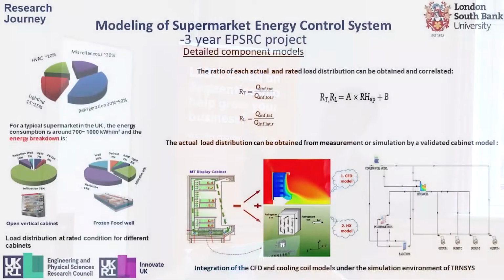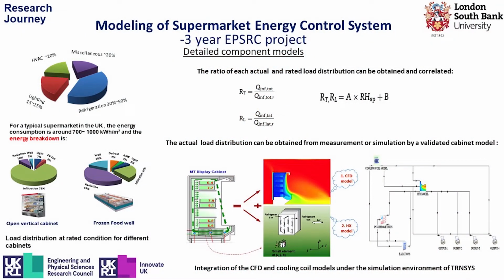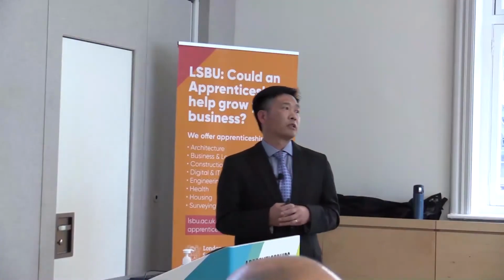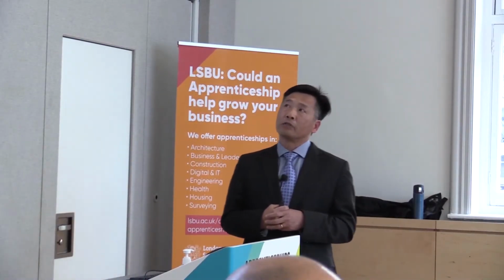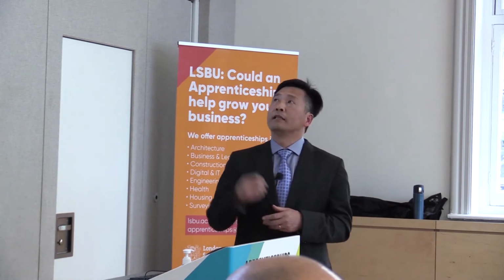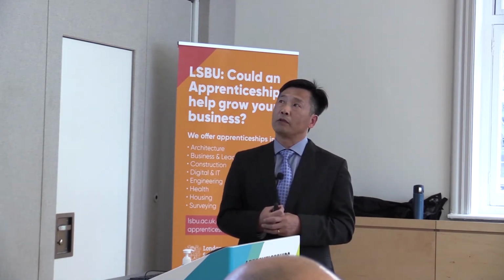So on the top left, you can see the energy breakdown of the supermarket energy control system. Refrigeration will consume about 30 to 50% of the overall energy consumption in the supermarket, and the lighting will be about 15 to 25%. And the HVAC system is about 20%, and the rest will be 20%.